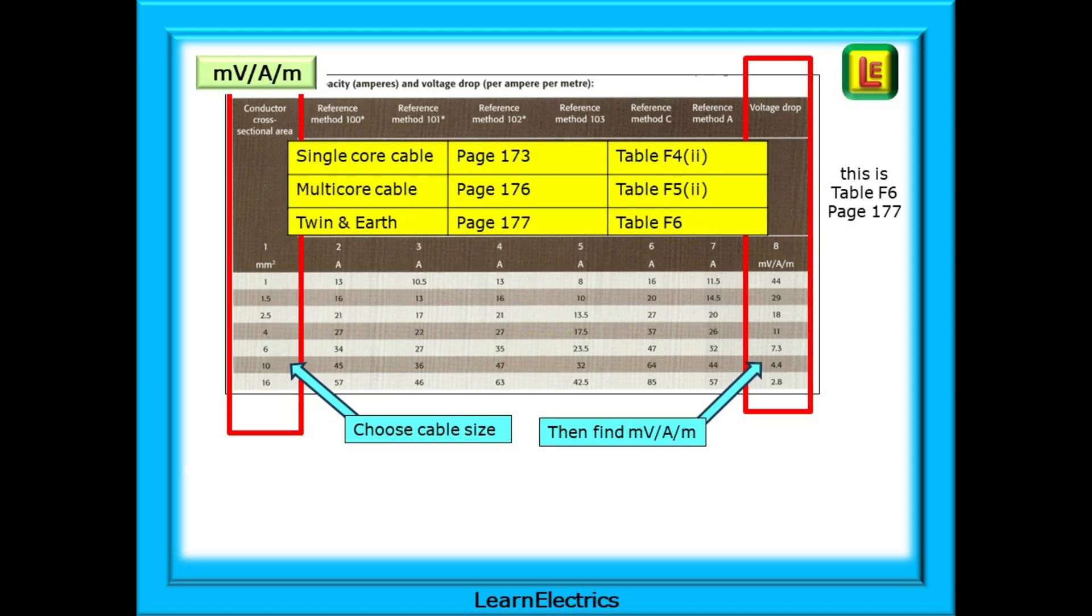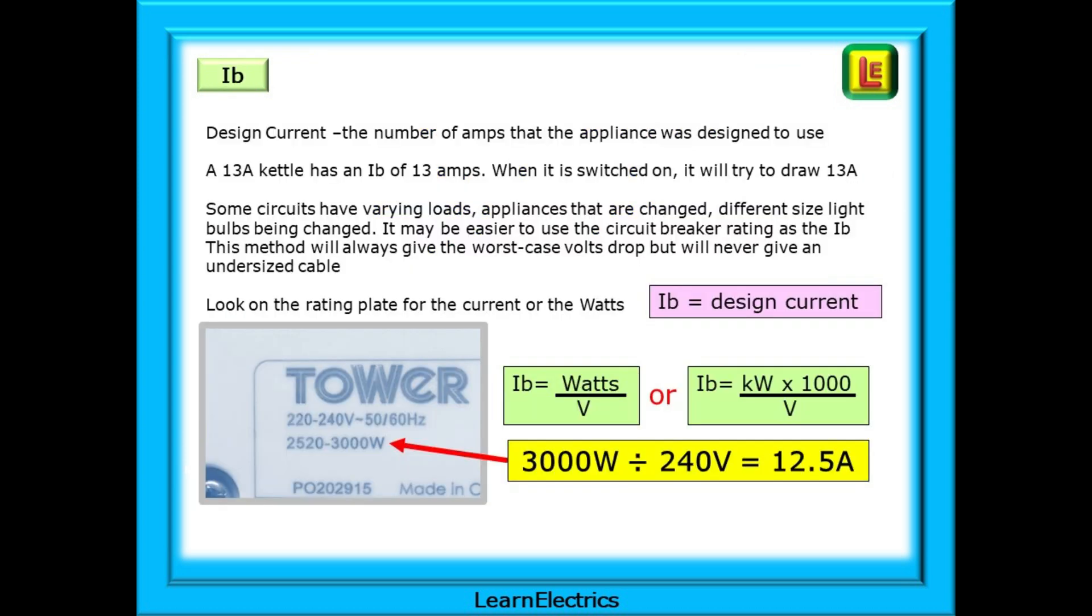The millivolts per amp per meter is a number specific to a certain size of conductor. Take a look at table F6 on page 177 and see the numbers in the rightmost column. The bigger the cable size, the less millivolts that are lost in the cable. We simply choose a cable size on the left and then look up the MVAM number on the right.